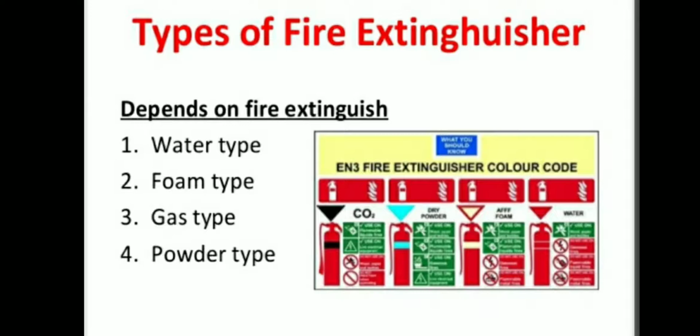Water type is normally, if you think of a water type fire extinguisher, we can use a water bucket. That is also a kind of water type fire extinguisher, but now they have designed it in a particular cylinder, which on top has a kind of CO2 cartridge. After puncturing the cartridge, the air comes in the cylinder and water gets pushed out through the nozzle and reaches the fireplace. That is known as water type.